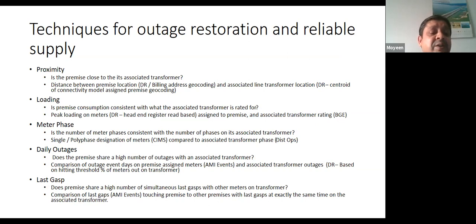But single phase meters are there, and we do have a network - we have GIS locations and we have alarms. So we should be able to correlate that and identify algorithms that tell us these consumers are on R phase, these consumers are on Y phase, and these on B phase. In that case we can help plan to move load from one phase to another.